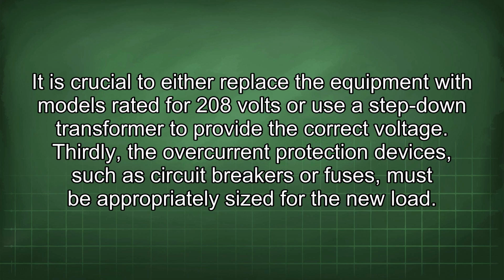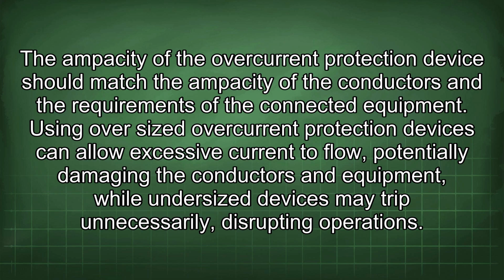Thirdly, the overcurrent protection devices, such as circuit breakers or fuses, must be appropriately sized for the new load. The ampacity of the overcurrent protection device should match the ampacity of the conductors and the requirements of the connected equipment. Using oversized overcurrent protection devices can allow excessive current to flow, potentially damaging the conductors and equipment, while undersized devices may trip unnecessarily, disrupting operations.